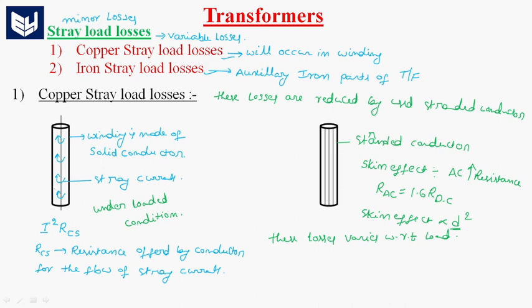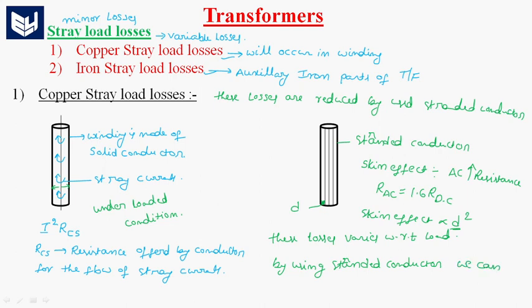Here the diameter of the solid conductor is more, whereas with a stranded conductor, only this smaller area is the diameter — so the diameter of the conductor is less. By using stranded conductor, we can reduce skin effect, and as a result we can reduce copper stray load losses in the transformer.